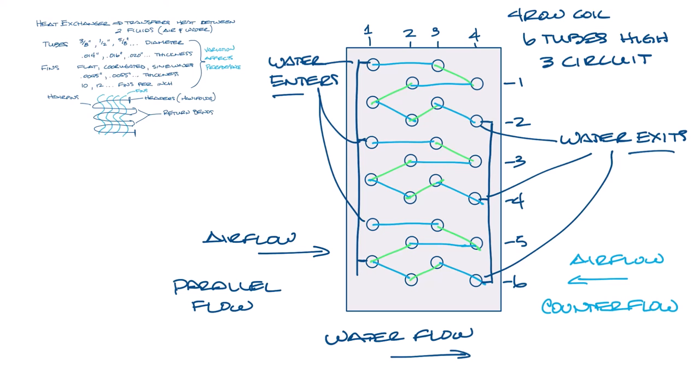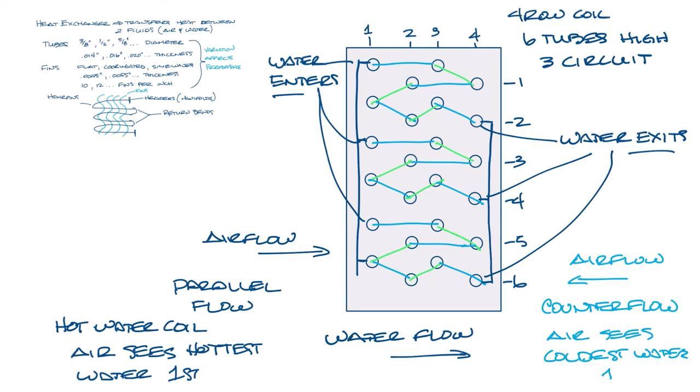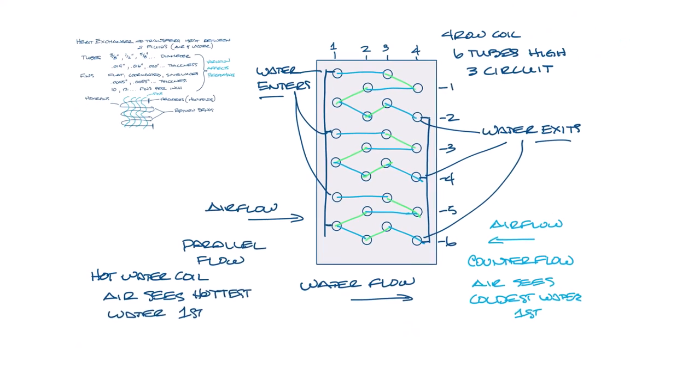So let's say this is a hot water coil. If the air flow is going left to right, and it's a parallel flow coil, the air would see the hottest water first. If this was used as a counter flow coil, the air would see the coldest water first.